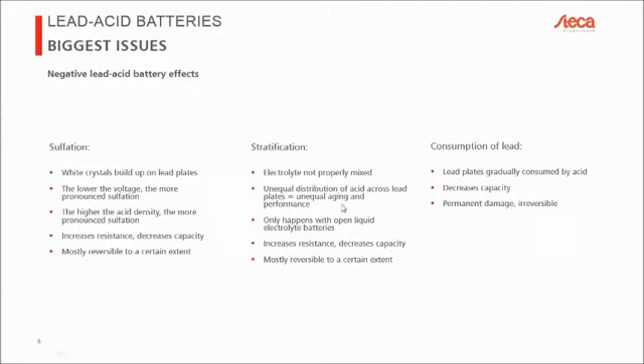That means we have unequal aging, lower performance, and this typically only happens with liquid electrolyte batteries, because if you have a gel, it's pretty much impossible for the water portion to split from the acid. This also increases resistance and decreases capacity, much like sulfation, and it's also pretty much a reversible effect.